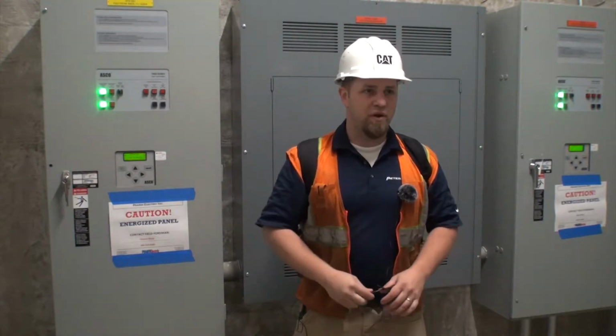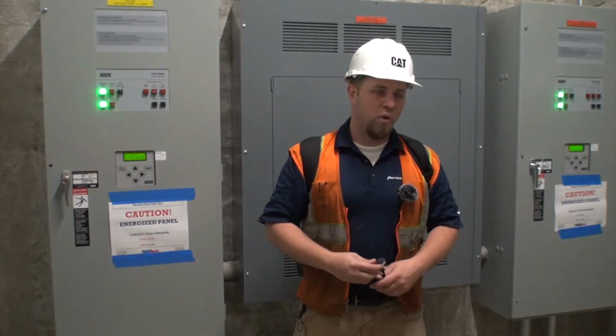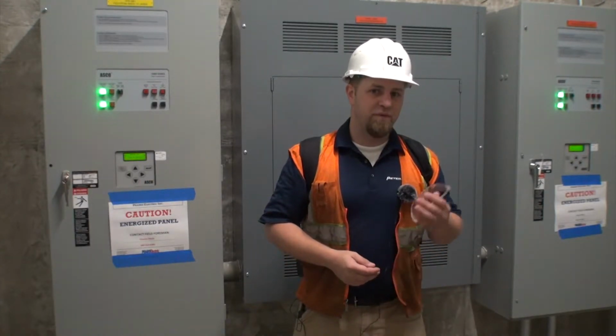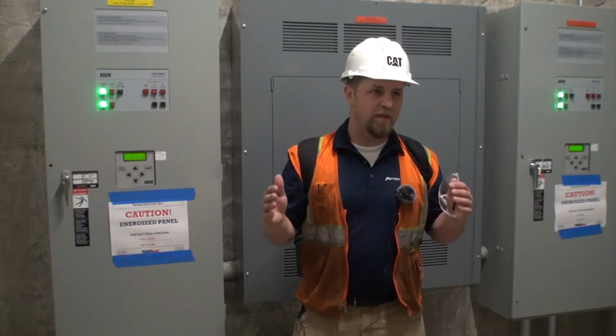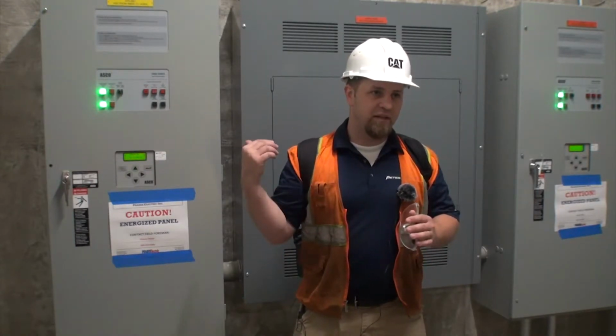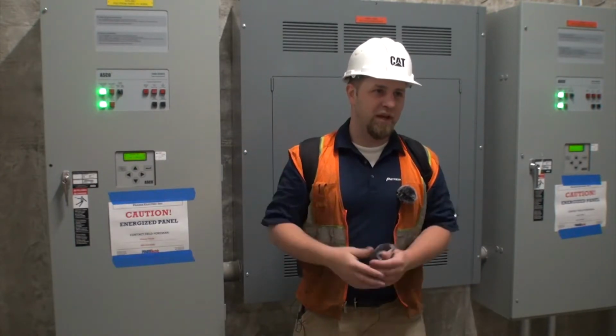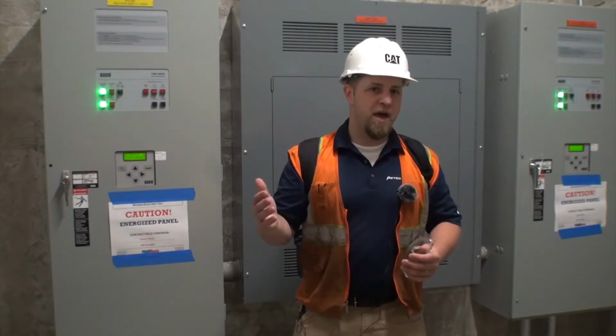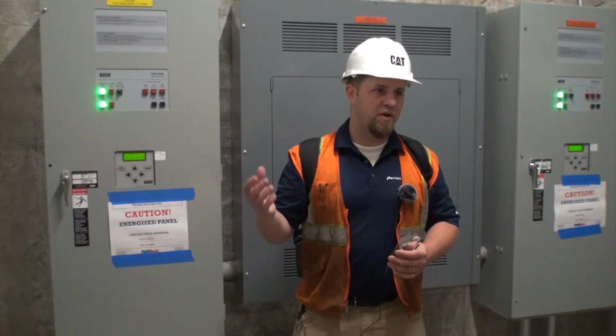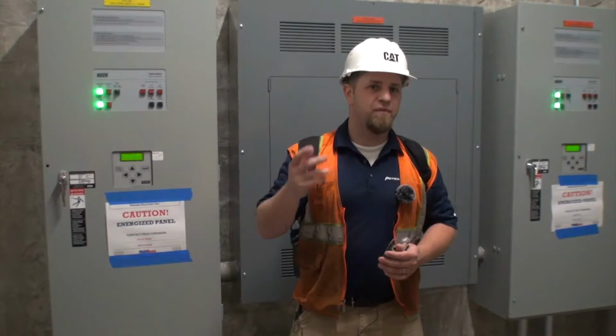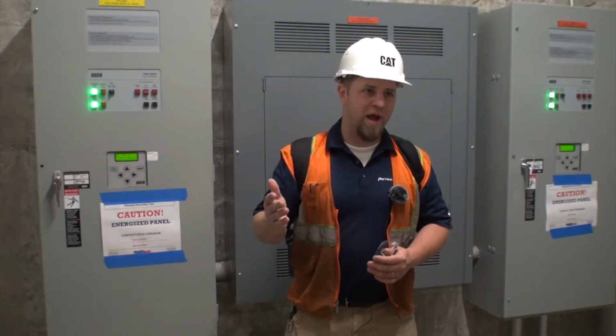Something else on ATSs: more than likely you have between a 15-minute and a 30-minute time window for the setting. Typical time is usually 15 minutes, but you can adjust that. When the power goes out, it flickers, and every time it flickers, it starts that timer back over again.